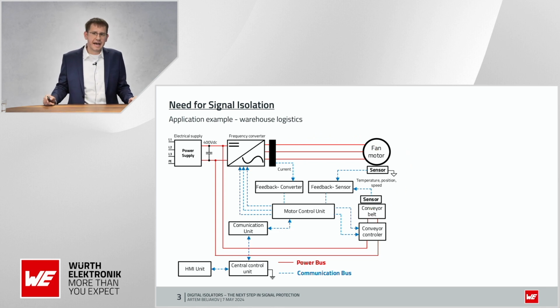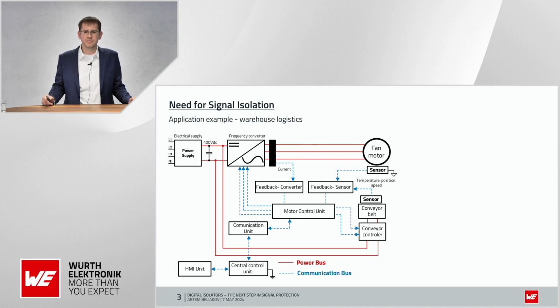Physical parameters like temperature, speed, voltage, and many others are measured by different sensors in the field and forwarded to the main central control unit. But the problem here is that, for example, the distance between the temperature sensor of the motor and the central control unit can reach several tens of meters. This means long wires, and also that measured signals can be disturbed by potential differences on the line. We definitely need to organize some isolation barrier between the two devices to prevent ground potential differences.